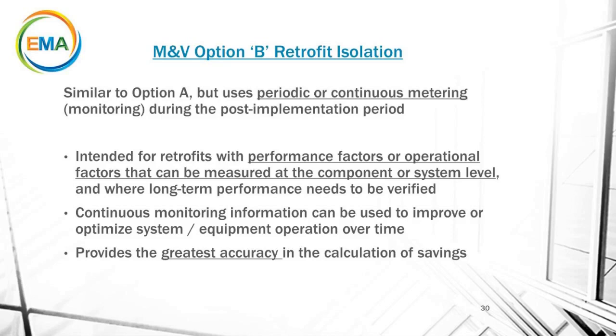Continuous monitoring information can be used to improve and optimize the system. Hey, this is what I intended. This is where it should be running, energy efficiency wise, in spring versus summer versus fall. Do I have some seasonality in there I need to improve on? It really helps you get through that whole performance cycle. And it provides the greatest accuracy in the calculation of savings because you're monitoring continuously. That's real data, and you can adjust that accordingly for degree days and environmental factors.